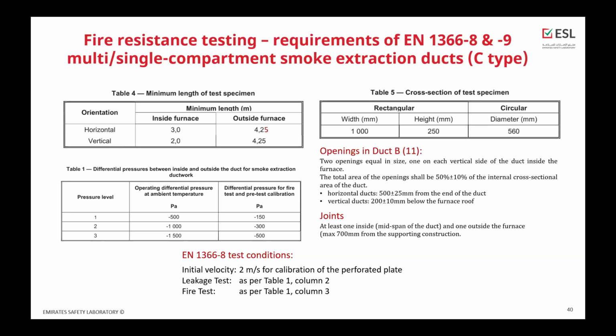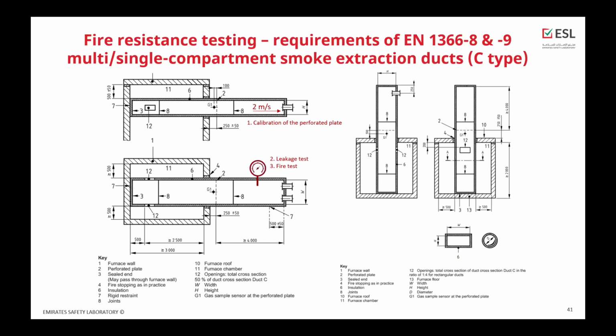Duct C construction is quite similar to duct B, and table 1, which is presented here, shows you the pressure levels which you need to choose before we start testing. Most clients use pressure level number 3, which gives you the widest scope of application for your duct. This means that under ambient temperature, the leakage of the duct is measured with 1500 pascals of underpressure inside the duct, and during the fire test we use 500 pascals inside the duct.